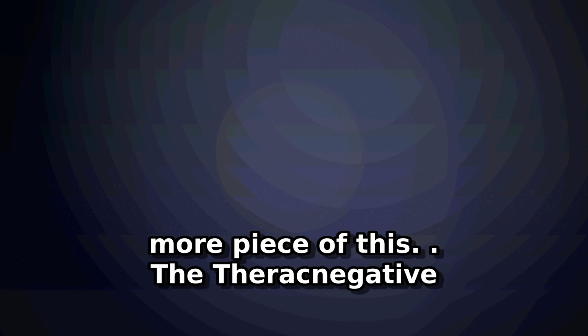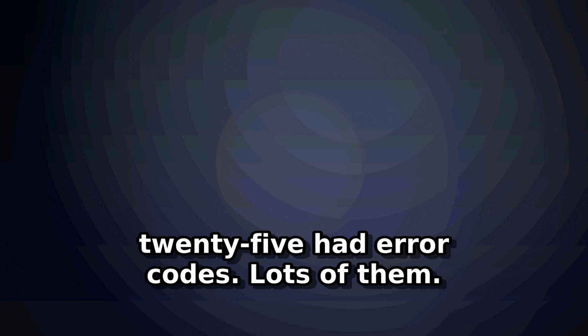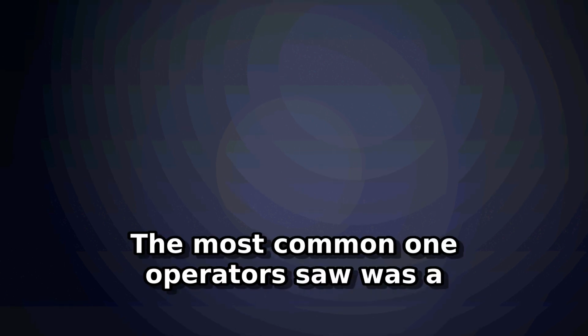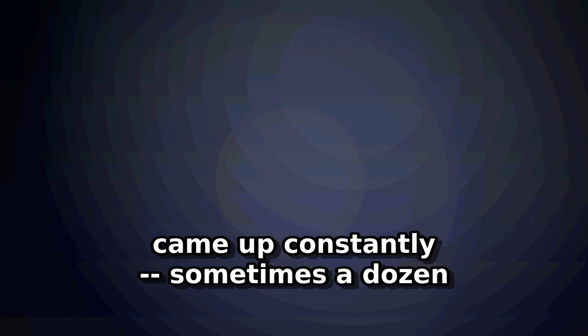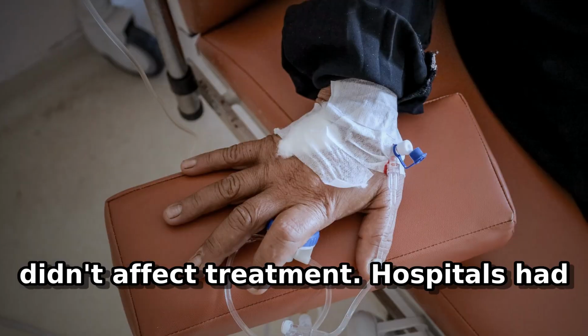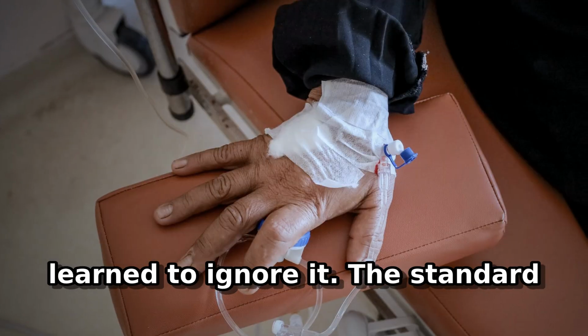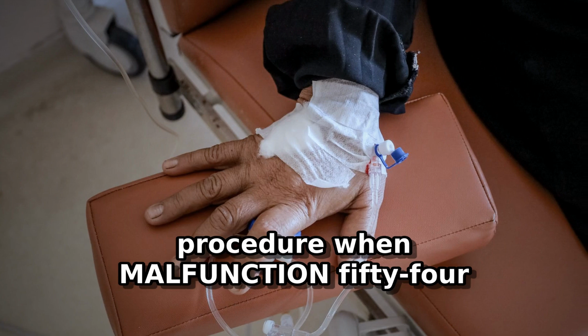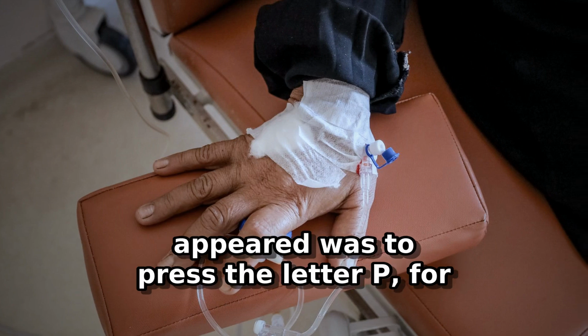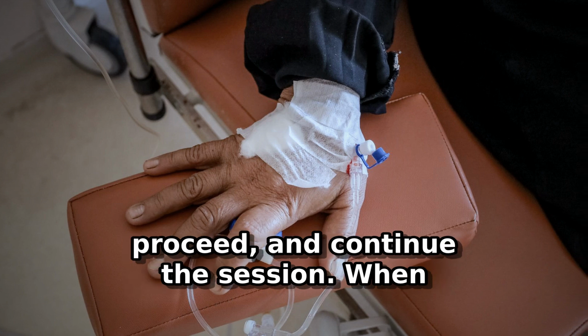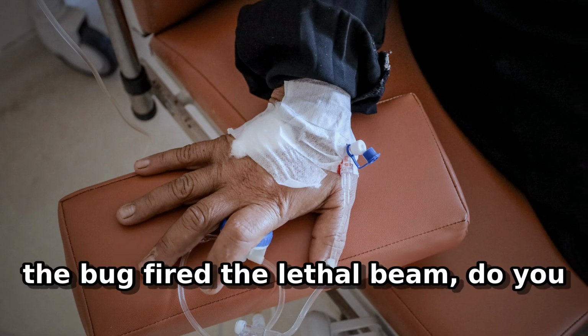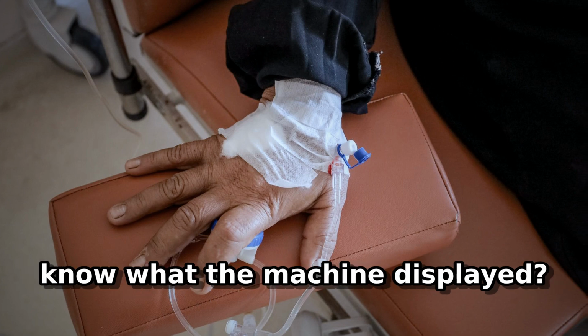There's one more piece of this. The Therac-25 had error codes, lots of them. The most common one operators saw was a code called malfunction 54. It came up constantly, sometimes a dozen times a day, for minor issues that didn't affect treatment. Hospitals had learned to ignore it. The standard procedure when malfunction 54 appeared was to press the letter P for proceed and continue the session. When the bug fired the lethal beam, do you know what the machine displayed?